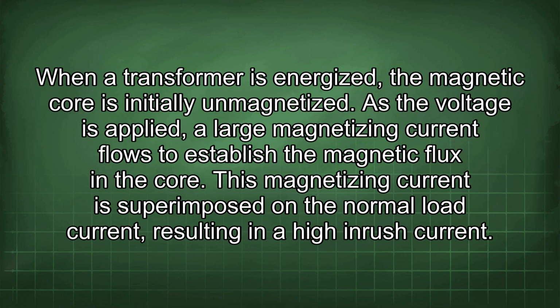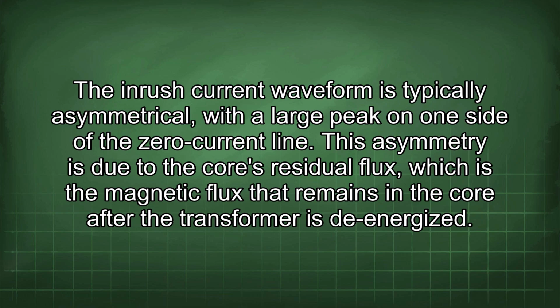When a transformer is energized, the magnetic core is initially unmagnetized. As the voltage is applied, a large magnetizing current flows to establish the magnetic flux in the core. This magnetizing current is superimposed on the normal load current, resulting in a high inrush current. The inrush current waveform is typically asymmetrical, with a large peak on one side of the zero current line.